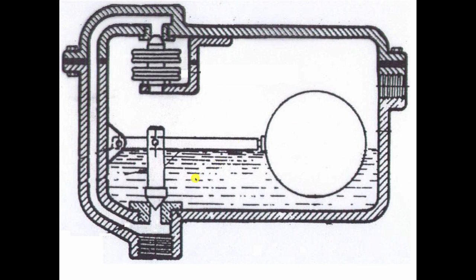Float and thermostatic trap is both normally closed on the water side and normally open on the thermostat side. So air comes through here, goes past the thermostat which is normally open and vents itself somewhere downstream. Steam comes in and shuts that trap. It's the same type of device that you'll find inside of the thermostatic radiator trap. Once that's closed, the steam's rattling around, it's got nowhere to go.